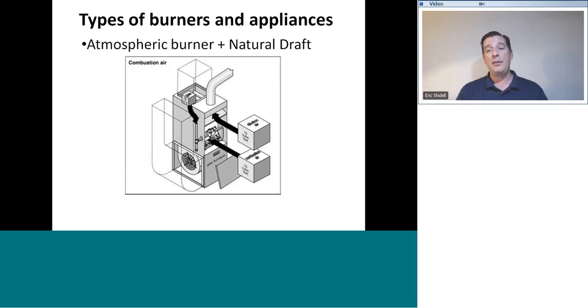If you take a pipe, stick it straight up in the air, and you make it long enough, it will automatically start drawing upwards. If the bottom end of it is inside of a building and the other end is outside of a building, this will create what's known as stack effect. A couple of things contribute to stack effect. If my flue is standing straight up and down like this, up in the air above the house, and wind is coming across it in this manner, that is going to increase the amount of draw on the flue as air moves across the top of that pipe.